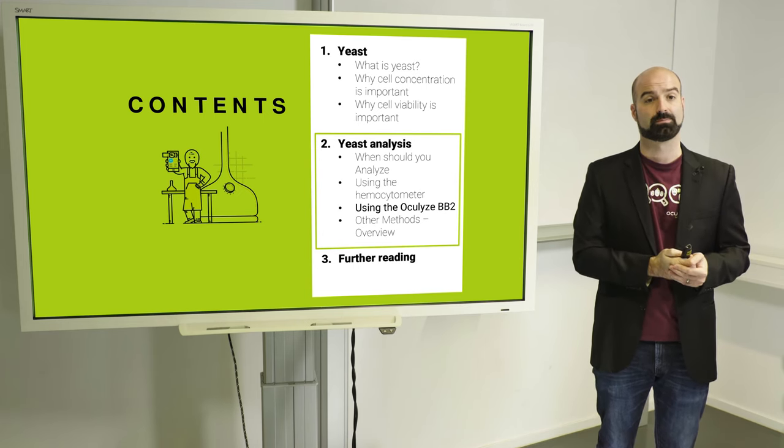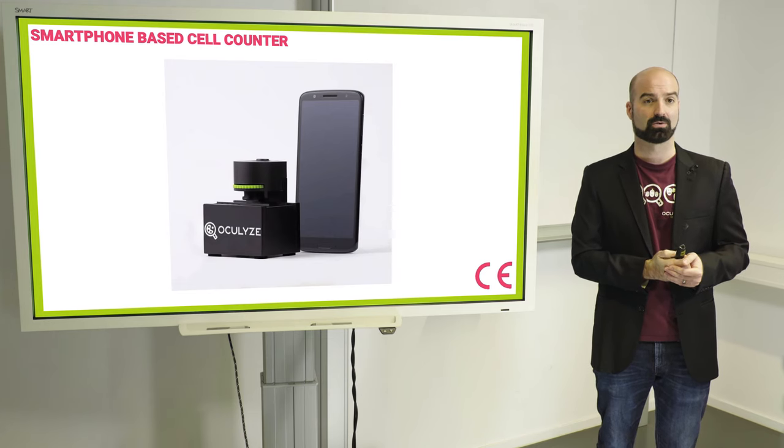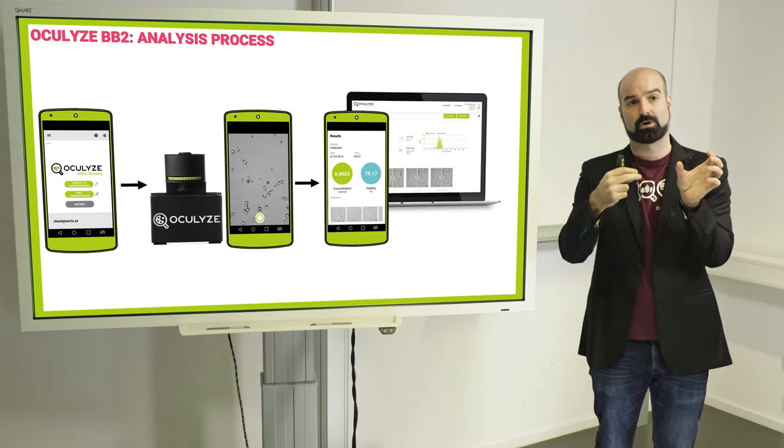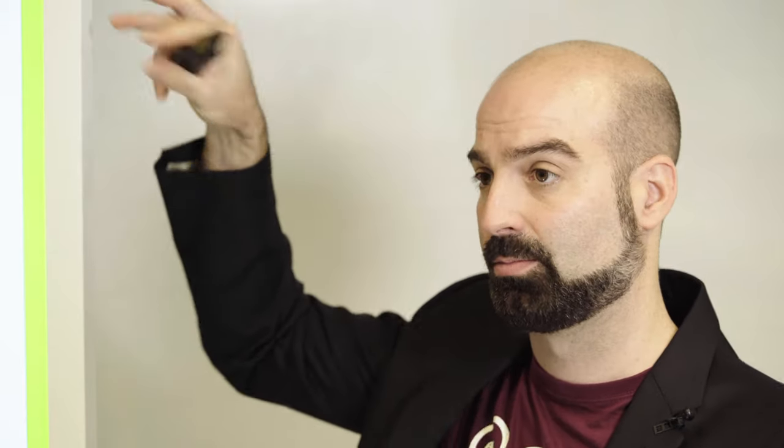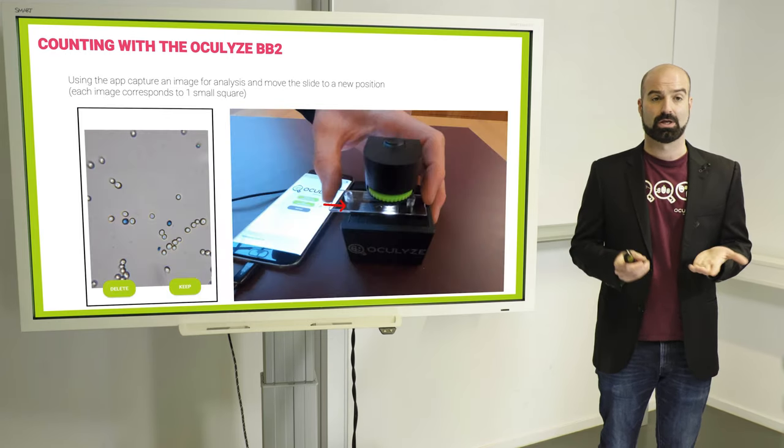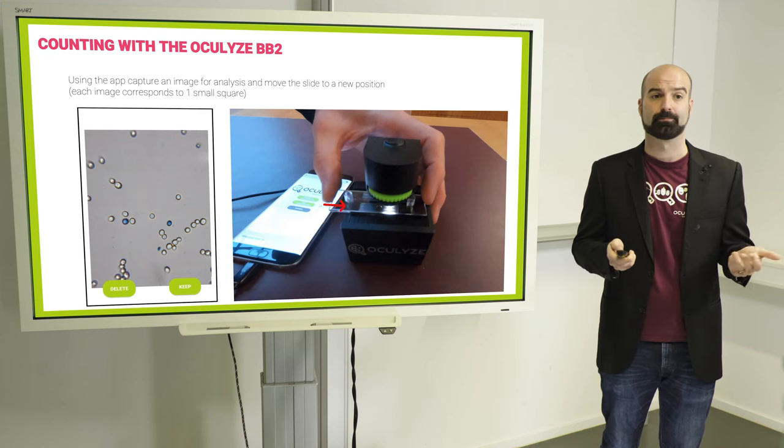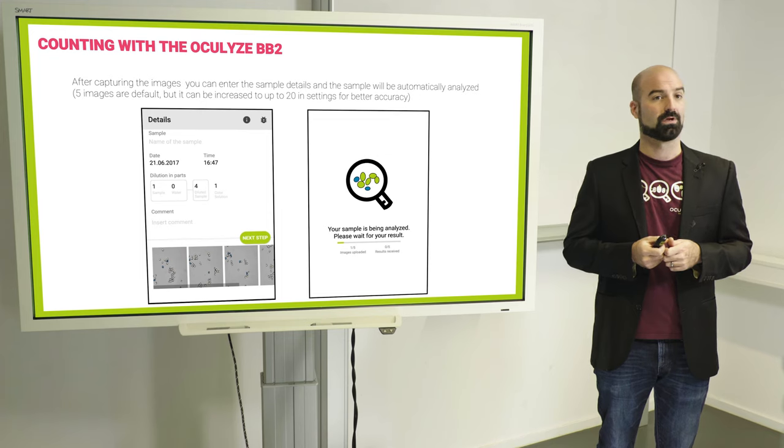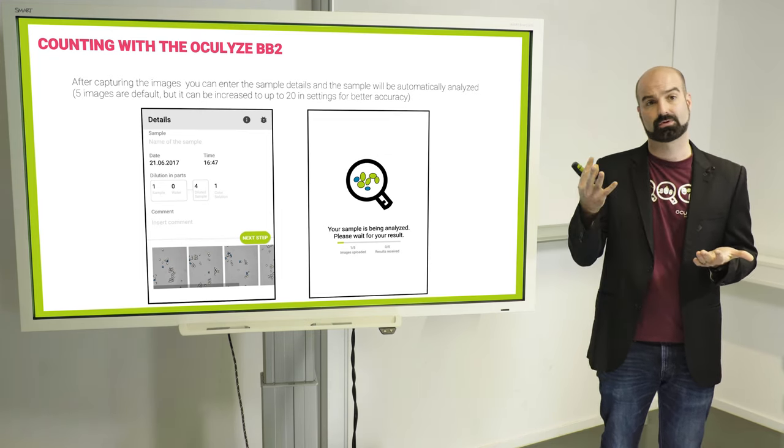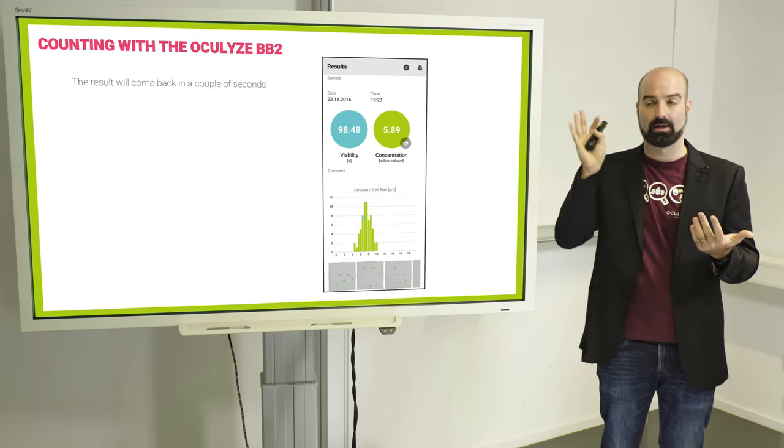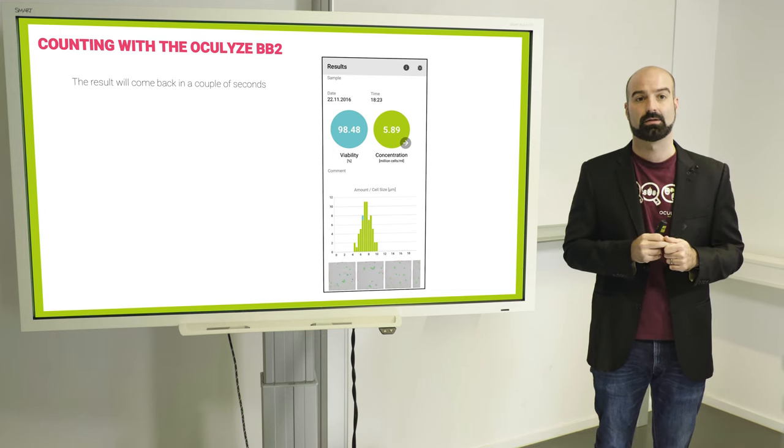Now we'll come to our own product, which is the Oculyze BB2. So this is what it looks like. Basically, it's a mobile microscope that you use with a smartphone. And the way it works is you open our app. Then you connect our smartphone. You take images. They're sent to the cloud, processed with image recognition, and then you get the results back. Or if we go step by step, first you focus the sample using a wheel. Then you get the image. And each image you take is like one of the squares on the hemocytometer. And you can take quite a few if you want, up to 20. Default is 5 like with the hemocytometer. After you're done with your images, they're sent to the server. And then it's processed in the cloud. And within a couple of seconds you will get the results back on the device.